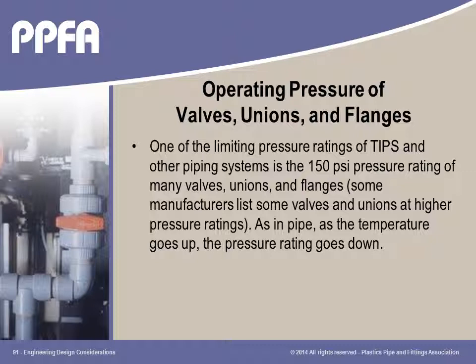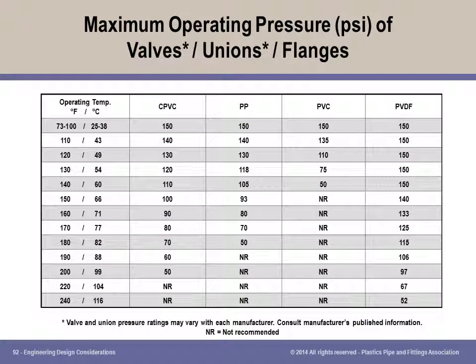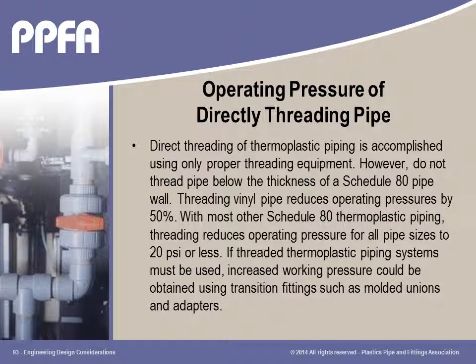Thermoplastic valves, unions, and flanges tend to limit the pressure in a thermoplastic piping system. For many of these products, 150 psi is the maximum working pressure rating at ambient temperature. Some products, valves in particular, may have higher pressure ratings, but to be sure, check with the manufacturer. As with pipe, the working pressure of valves, unions, and flanges must be derated as temperature increases. Each manufacturer might have slightly different temperature correction factors for their products. Check with the manufacturers. Pipe threading decreases the working pressures of all thermoplastic piping. Where possible, avoid direct threading thermoplastic pipe.